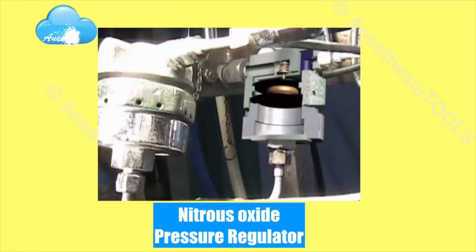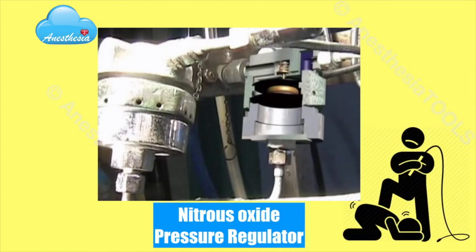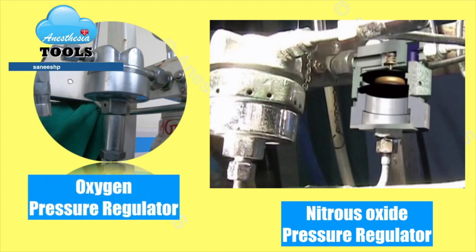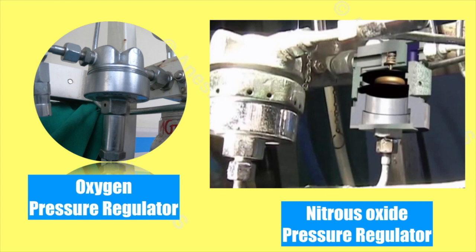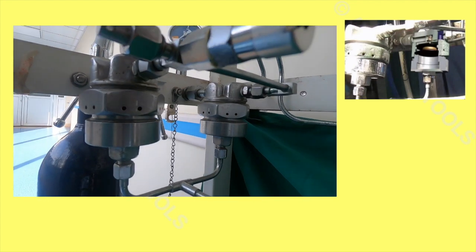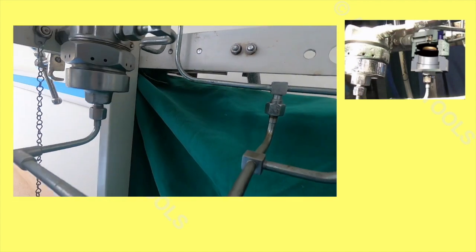Now, what is special about the nitrous oxide pressure regulator, and why is it called a slave regulator? From the external features, we can see that the oxygen pressure regulator has two chambers, while the one for nitrous oxide has three chambers. You can trace the inlet at the bottom of the nitrous oxide regulator to the oxygen pressure regulator output.